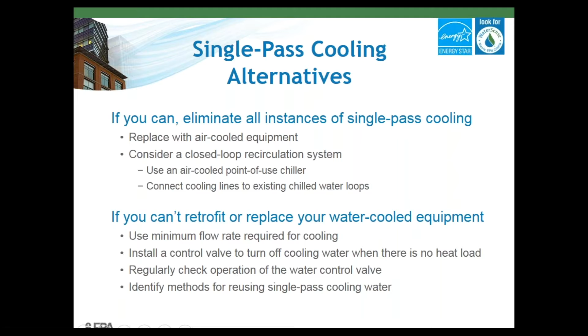If the system doesn't have a water control valve, you can install one to shut off cooling water when there is no heat load. The solenoid valves typically control this, but they can oftentimes need maintenance as well, so verify they're working and perform maintenance periodically. And in some cases, single-pass cooling water can be reused for another purpose, but it's best ideally to eliminate it where we can. Next slide.